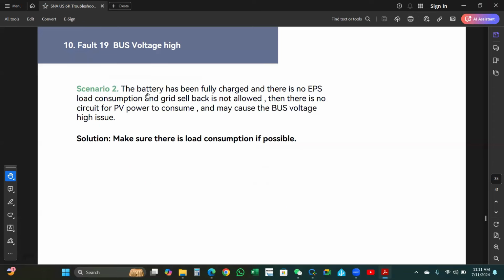Scenario 2: the battery has been fully charged and there is no EPS load consumption. Grid sellback is not allowed, so there is no circuit for the PV power to be consumed, and this may cause the bus voltage high issue. Make sure there is a load consumption if possible. Okay, that makes sense.